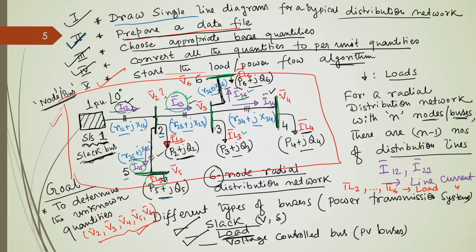That is basically the application of Kirchhoff's current law and Kirchhoff's voltage law in an iterative way. This is called forward backward sweep load flow or power flow analysis. In order to discuss this approach, I took an example of a simple 6 bus or 6 node distribution network.